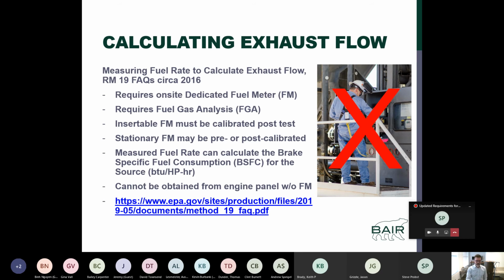Another way to get those estimated fuel rates is here at the engine panel. You do not want to use those brake specific fuel consumption numbers. There are, I think, some new panels that will give you that fuel meter reading that is actually tied to a dedicated fuel meter. Make sure that if you're getting a brake specific fuel consumption number off of an engine operating panel, it does come from a directly associated fuel meter for that engine or for that source. Otherwise, that number you're seeing in there is simply a calculated number, and it's no different than using a manufacturer's spec sheet or a program.